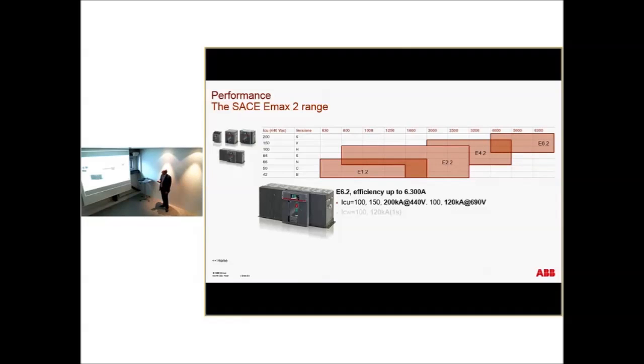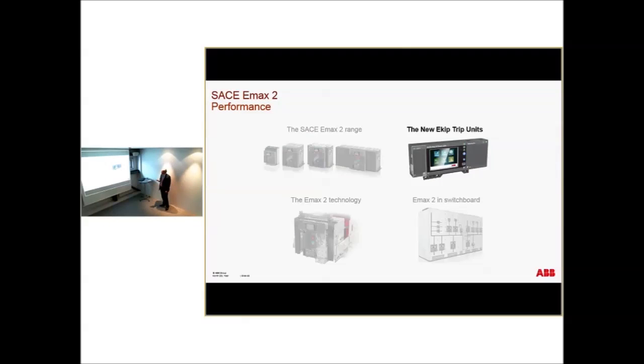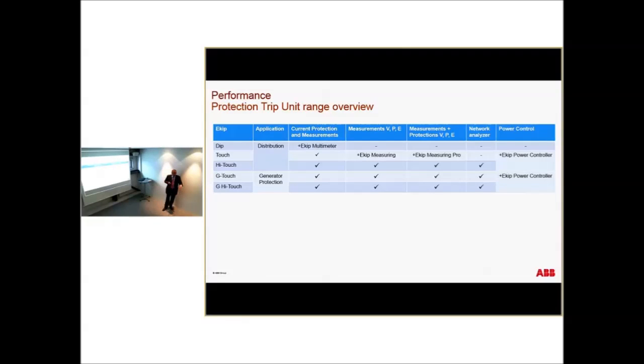This is the E6, the biggest one, and what we achieve is really amazing. It's the highest value in the market, 200 kA at 440 volts. Icw 120 kA, and you have a structure that we put in parallel. In temperature rise, we are not far from the 6300. We have a small derating, but better than the present breaker. For the neutral, you can have a half pole or an entire pole.